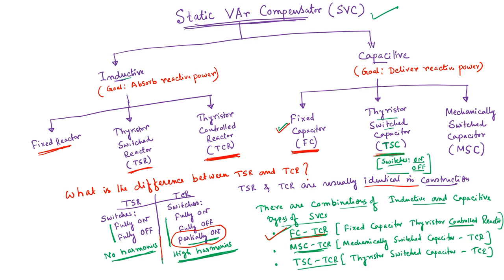To alleviate that, we need switchable capacitors. As we have seen, there are two types of switchable capacitor: one is mechanically switched capacitor, another is thyristor switched capacitor. When we have a mechanically switched capacitor coupled with this TCR — thyristor controlled reactor — the unit is called MSC-TCR, that is mechanically switched capacitor thyristor controlled reactor. Let me discuss briefly what it actually is.